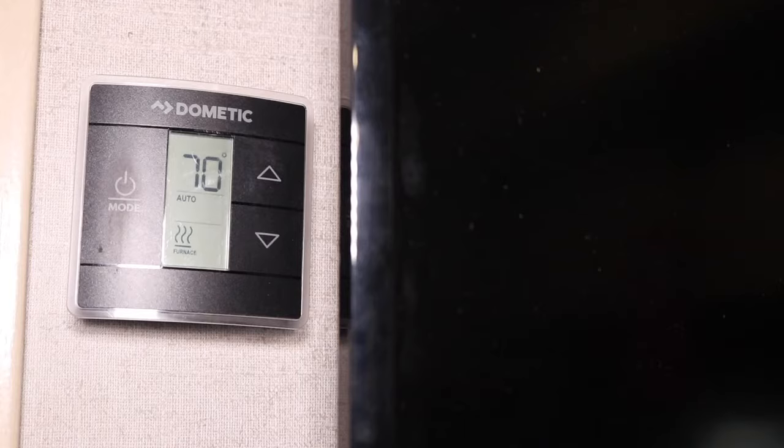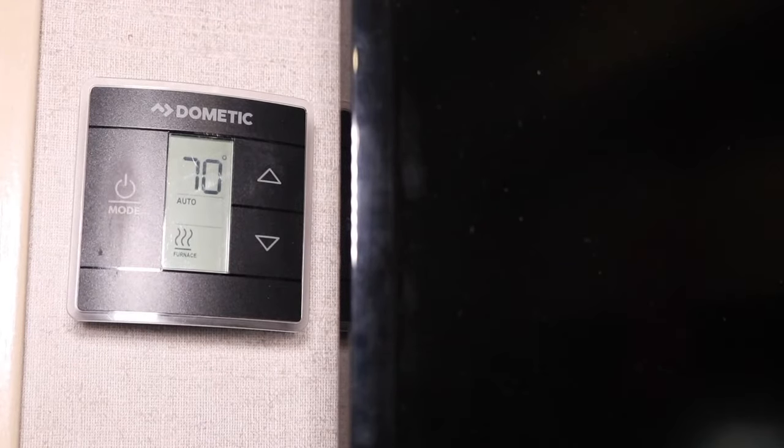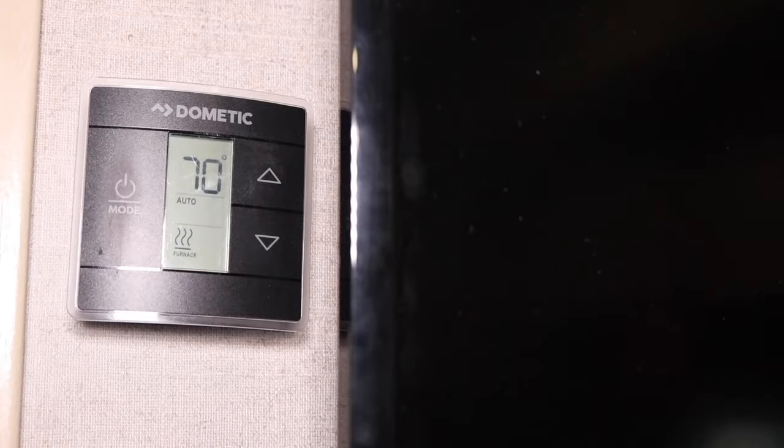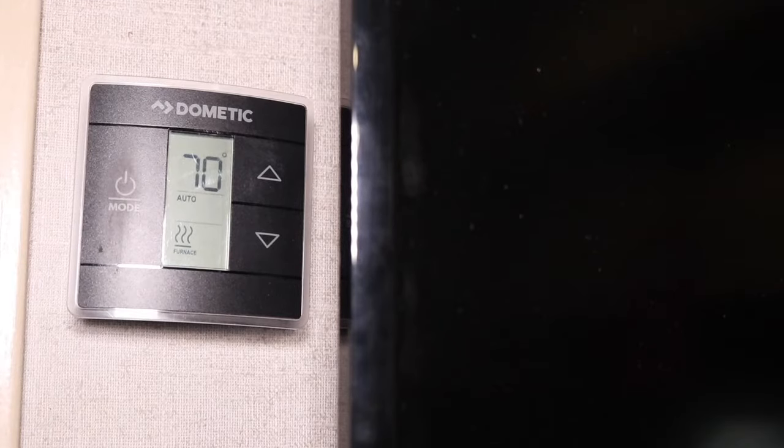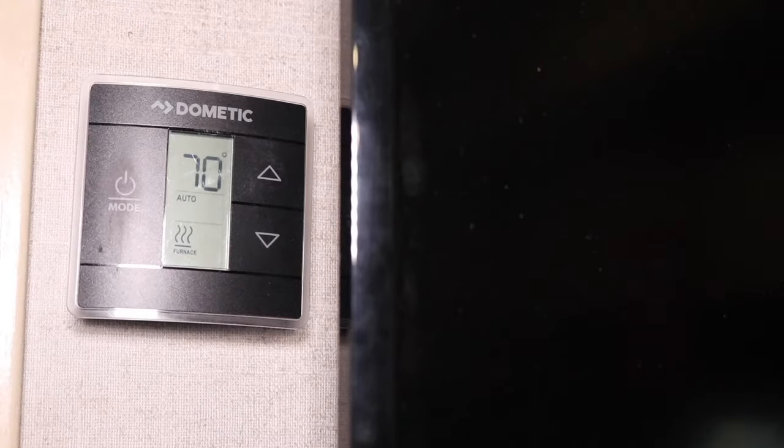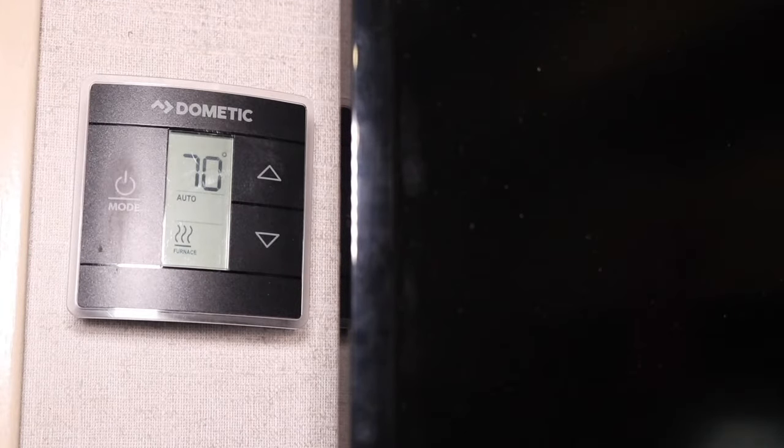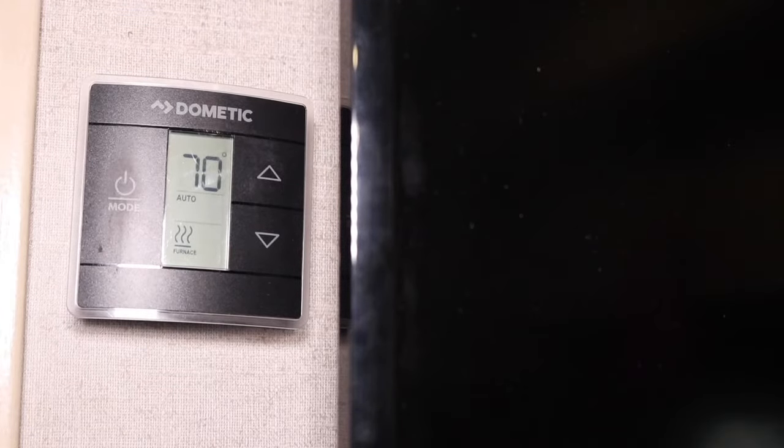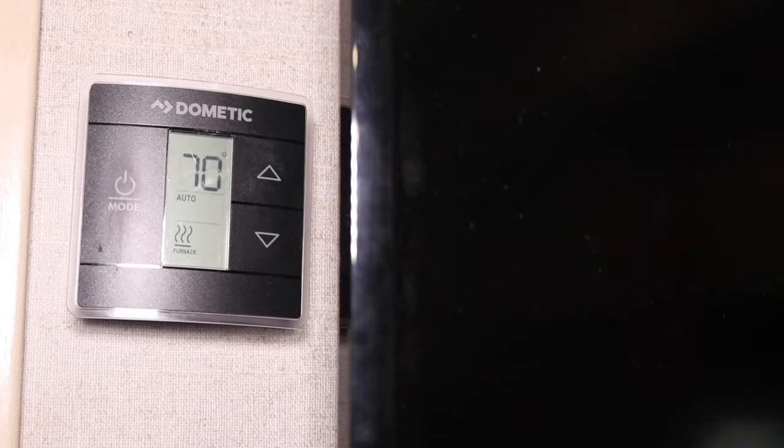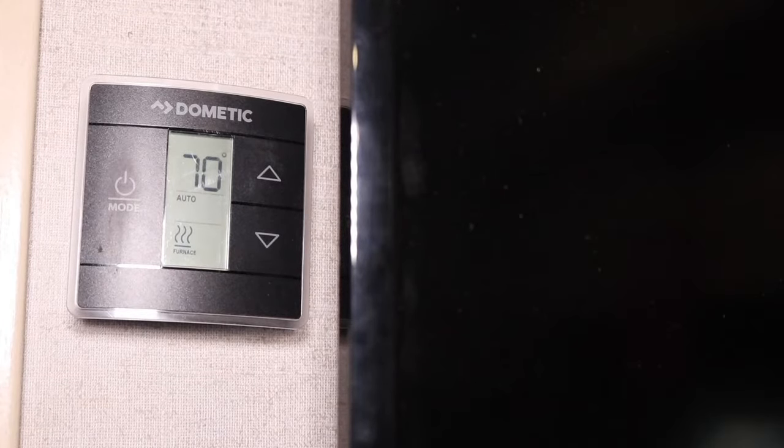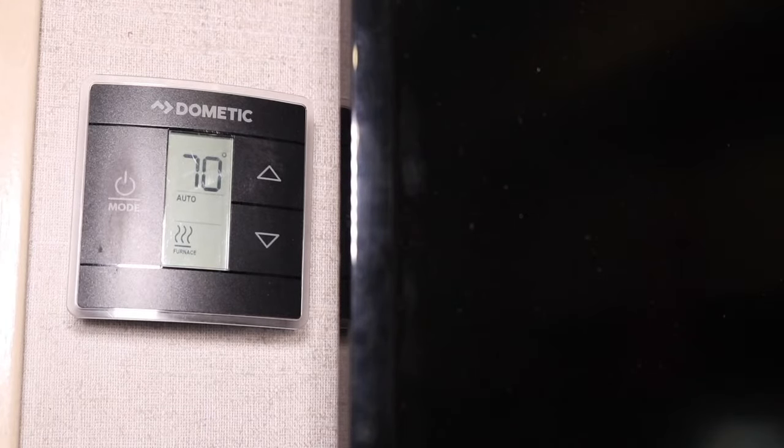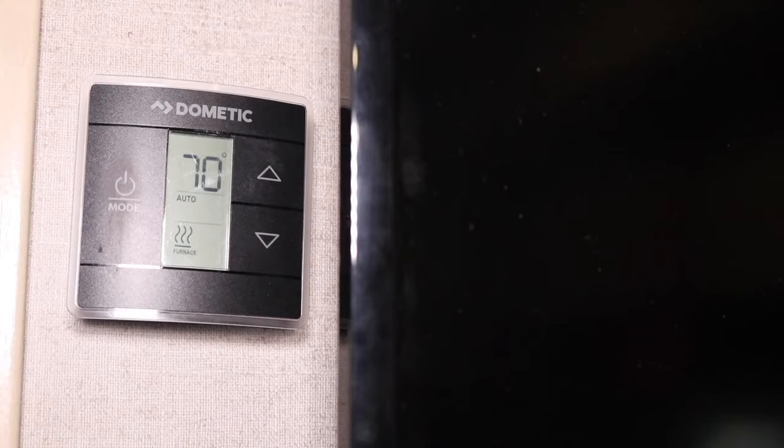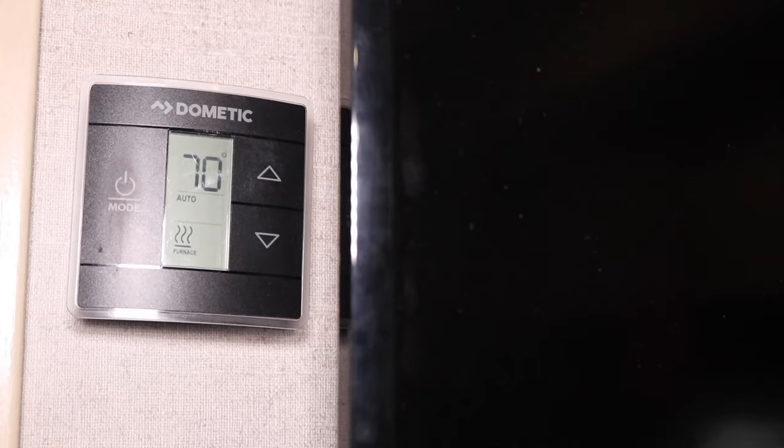That's why your fan doesn't turn off right away. And then if you want to turn it back on, that lockout period also makes sure that it doesn't kick on right away, so you don't have any problems with short cycling. That's also common in AC units. So if you turn your AC on for a minute and then turn it off, it might not turn back on for five to ten minutes depending on the lockout period on that model.